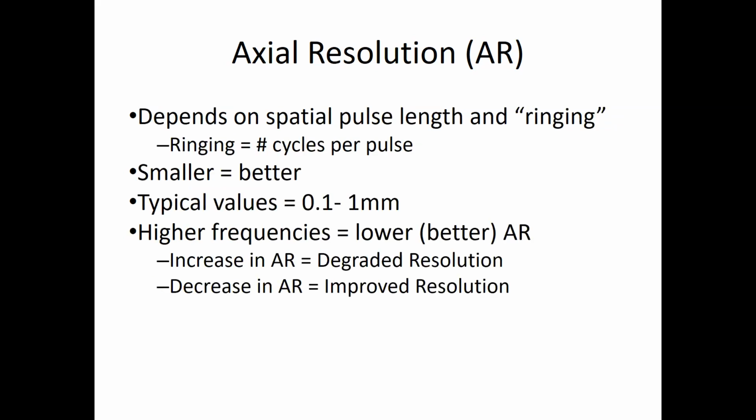So this comes back to our spatial pulse length. The longer my spatial pulse length, I'm going to see 2 structures as not separate, because my chirp is going out and it's coming back, but it's not chirping off of those things individually. And so I'm going to have a spatial pulse length and it's going to cover both of those structures and it's going to look like one large structure.